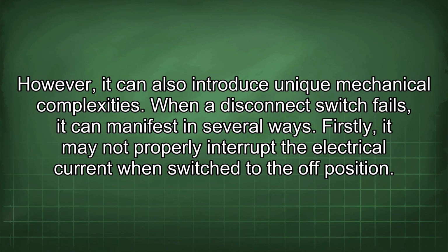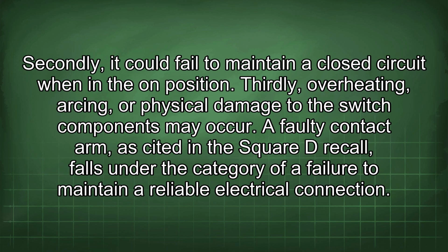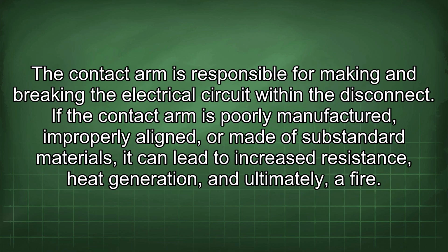When a disconnect switch fails, it can manifest in several ways. Firstly, it may not properly interrupt the electrical current when switched to the off position. Secondly, it could fail to maintain a closed circuit when in the on position. Thirdly, overheating, arcing, or physical damage to the switch components may occur. A faulty contact arm, as cited in the Square D recall, falls under the category of a failure to maintain a reliable electrical connection. The contact arm is responsible for making and breaking the electrical circuit within the disconnect. If the contact arm is poorly manufactured, improperly aligned, or made of substandard materials, it can lead to increased resistance, heat generation, and ultimately a fire.